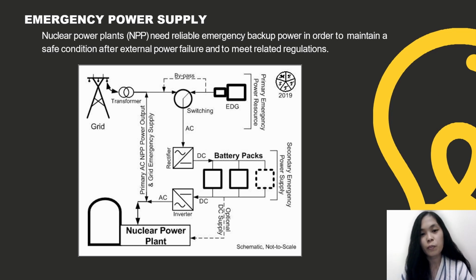The emergency power supplies of a nuclear power plant are built up by several layers of redundancy, such as diesel generators, gas turbine generators, and battery buffers. If necessary, the emergency power supply allows the safe shutdown of the nuclear reactor. Less important auxiliary pipelines are not supplied by these backups. Most of the required power is used to supply the feed pumps in order to cool the reactor and remove the decay heat after a shutdown.